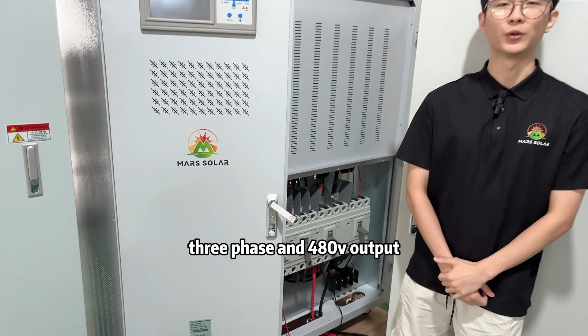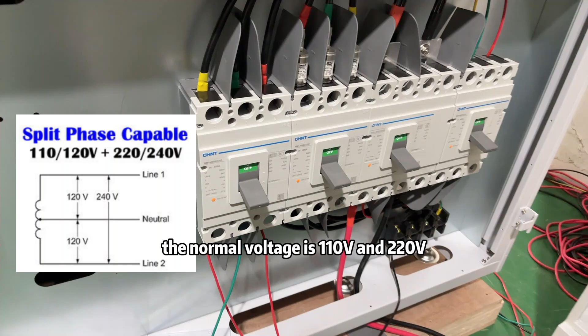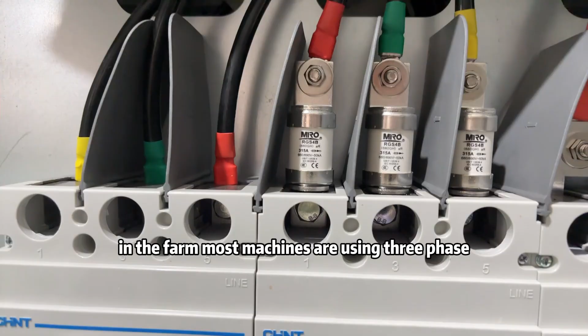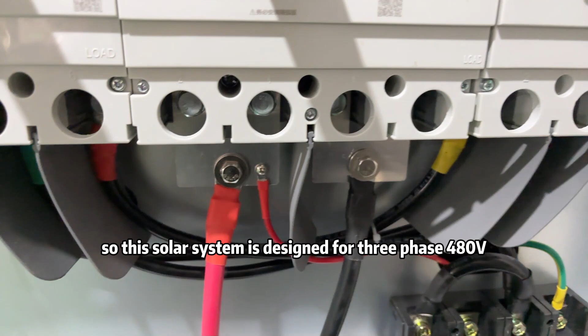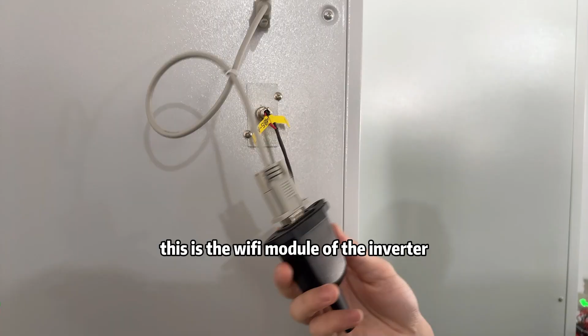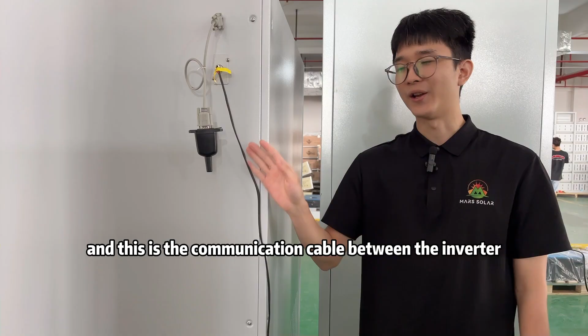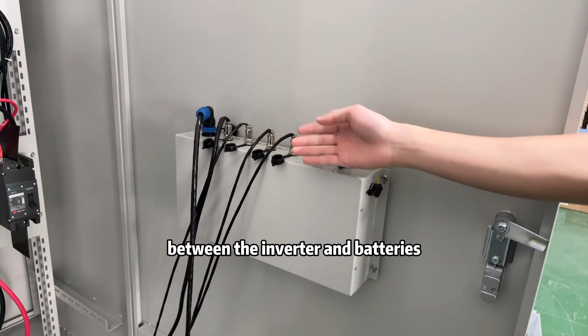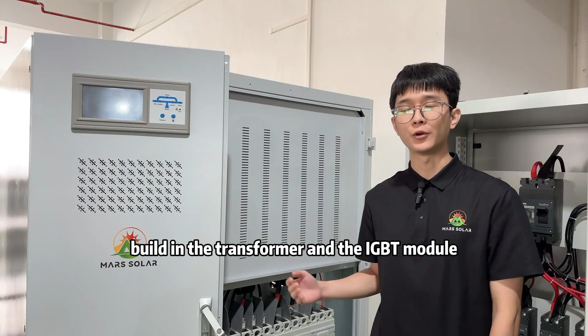This is a 150 kilowatt inverter, 3-phase and 480 voltage output. In the Caribbean Sea, the normal voltage is 110 and 220. In the farm, most machines are using 3-phase, so this solar system is designed for 3-phase 480 voltage. This is the Wi-Fi module of the inverter, and this is the communication cable between the inverter and batteries.